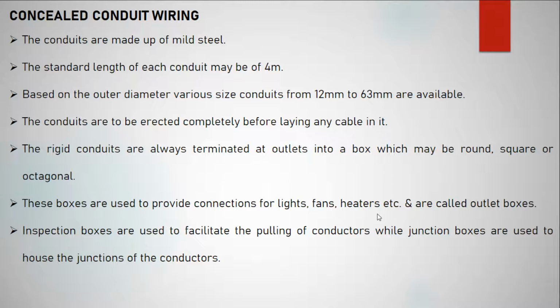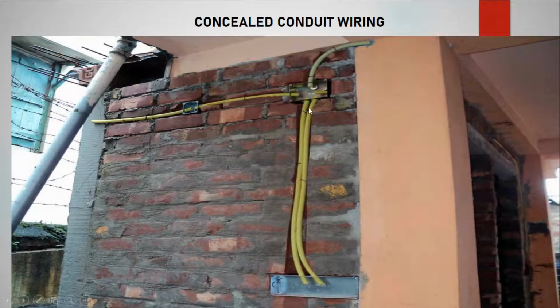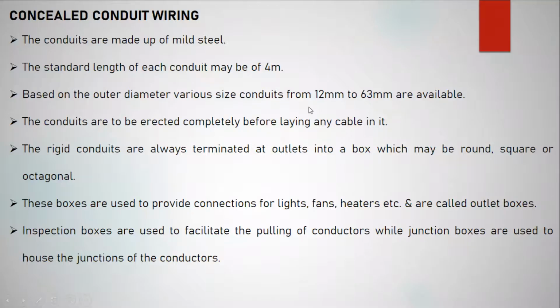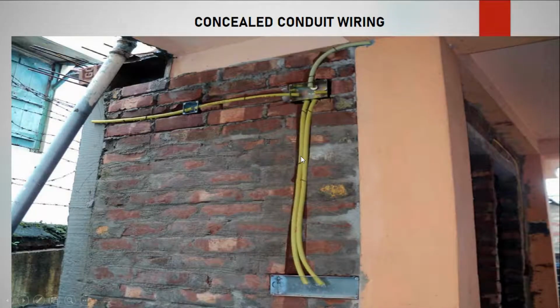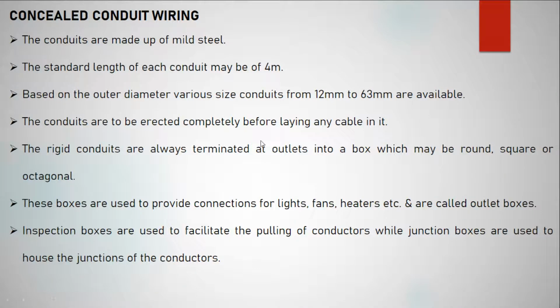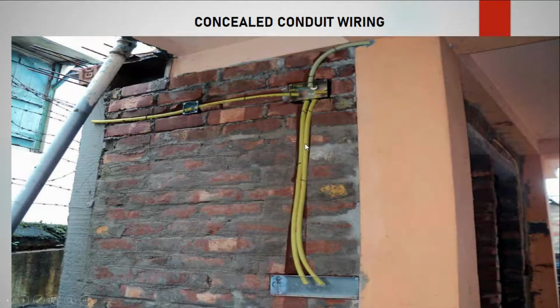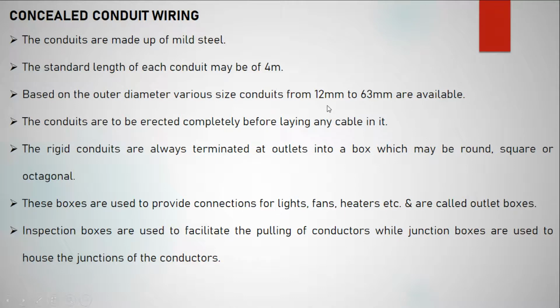The point is the concealed conduit wiring. The conduits are made of mild steel. Yes, actually it has to be mild steel. Nowadays they may use hard PVC conduits. The standard length of each conduit may be 4 meters. If you go to a hardware shop and ask for conduit, they will ask you how much length you want. One length means nearly 4 meters. Based on the outer diameter, various size conduits from 12 mm to 63 mm are available. The diameter varies from size to size.